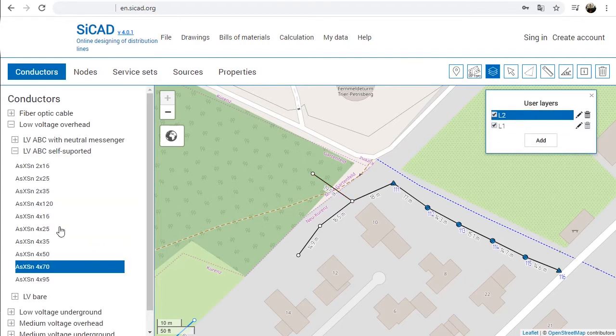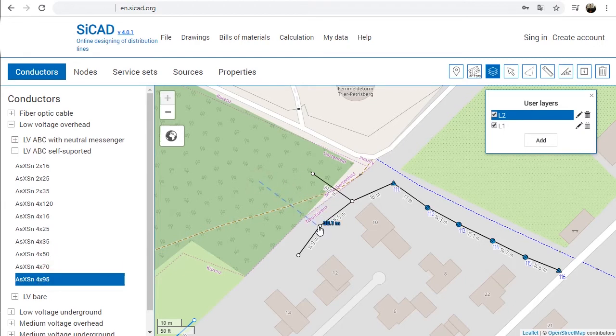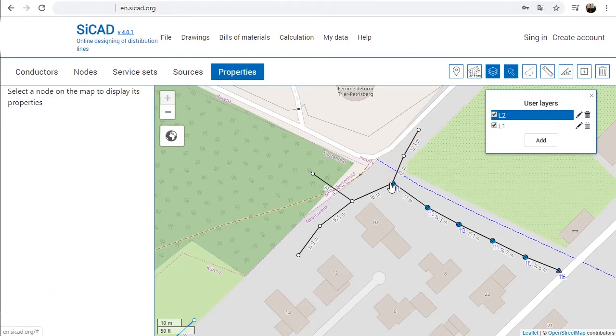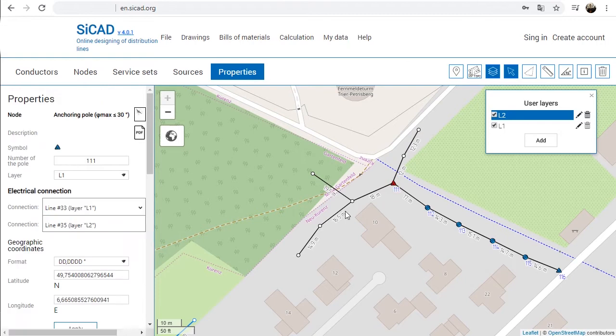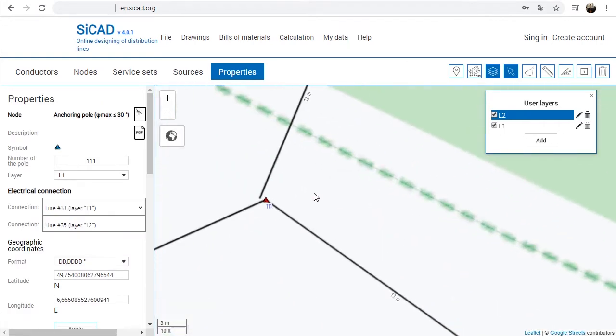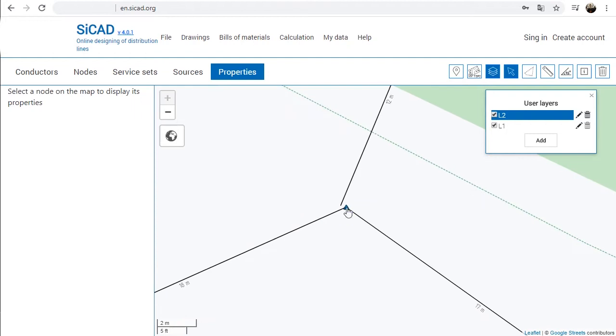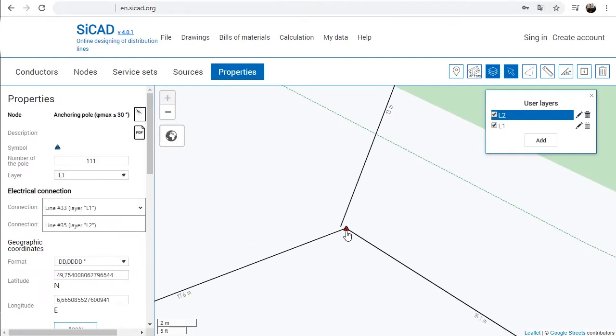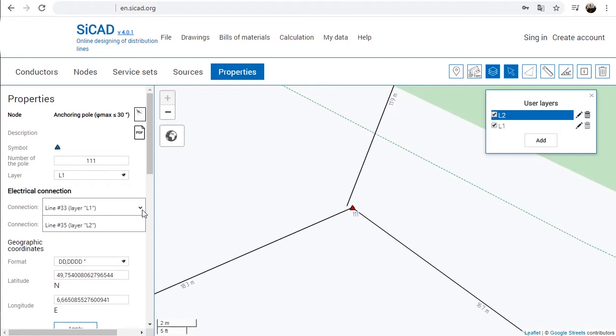If the lines are located on different layers, they cannot be attached without an installed node. Installation of a node allows attaching lines from another layer at that point. In the case of lines from different layers attached to a common node, lines are considered not electrically connected until they are connected in the properties of the common node.